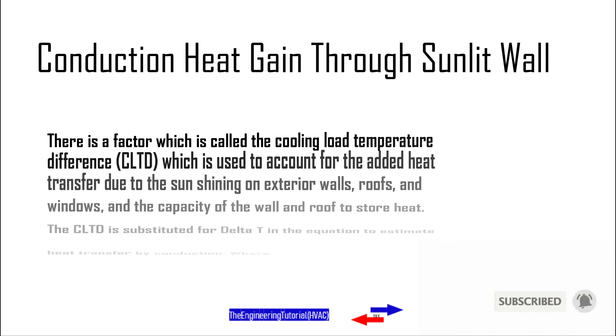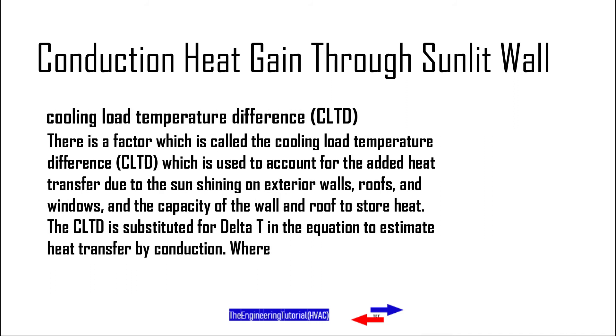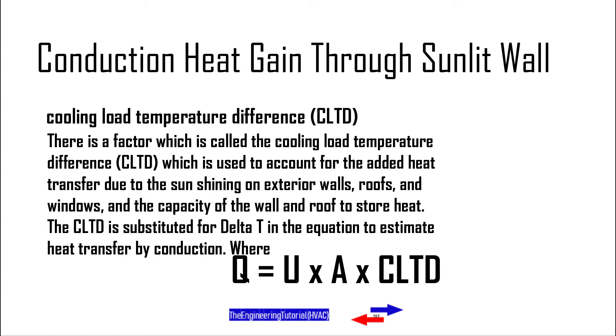Conduction heat gain through sunlit surfaces is estimated using the Cooling Load Temperature Difference, or CLTD. The CLTD is a factor used to account for the added heat transfer due to the sun shining on exterior walls, roofs, and windows, and the capacity of the wall and roof to store heat. The CLTD is substituted for delta T in the conduction heat transfer equation: Q equals U times A times the Cooling Load Temperature Difference, CLTD.